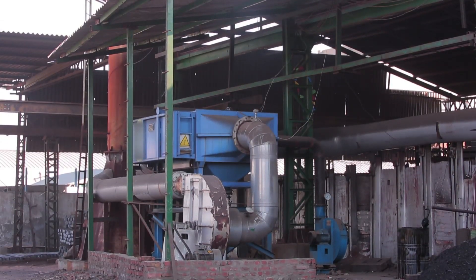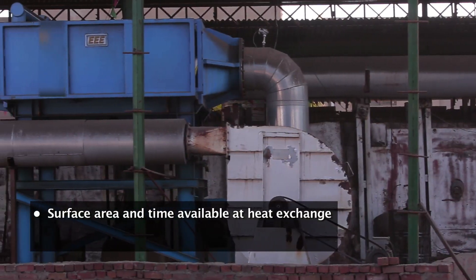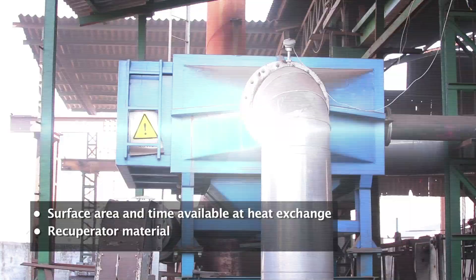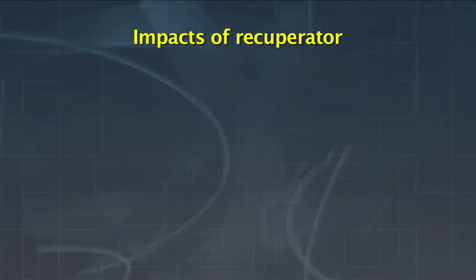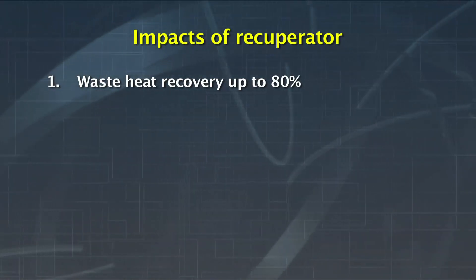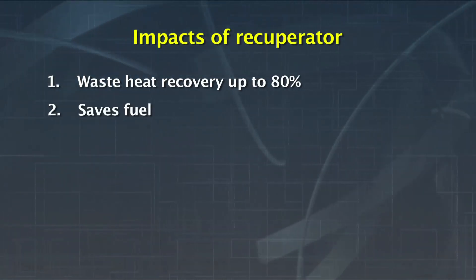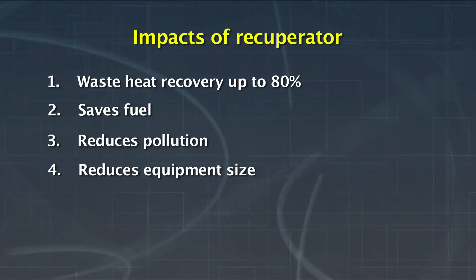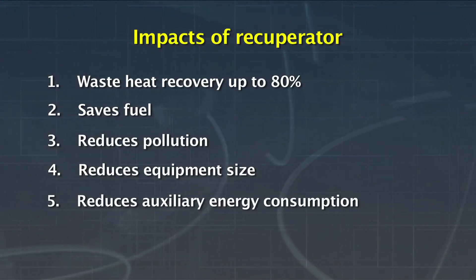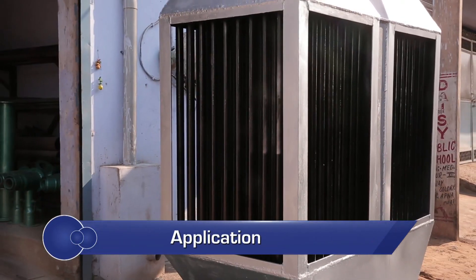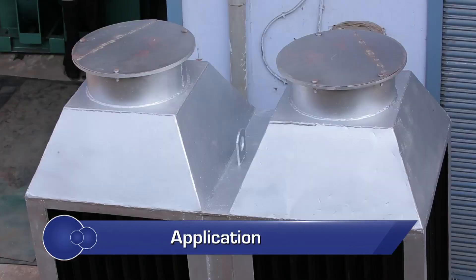The recuperator efficiency depends on two important parameters: surface area and time available for heat exchange, and recuperator material. The impact of recuperators includes waste heat recovery of up to eighty percent of the exhaust flue gas temperature, fuel savings, reduced pollution, reduced equipment size, and reduced auxiliary energy consumption.